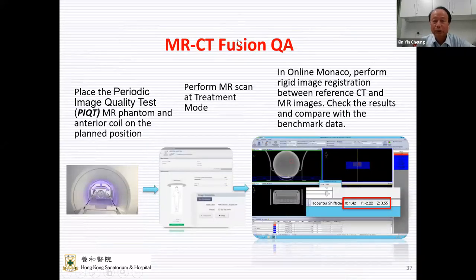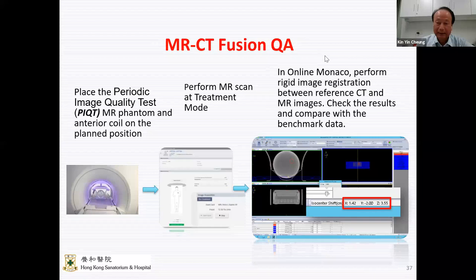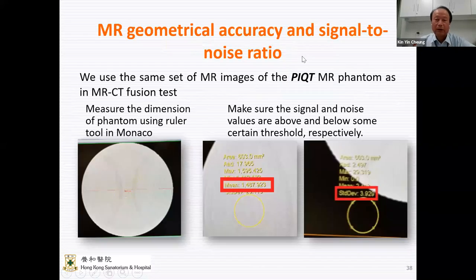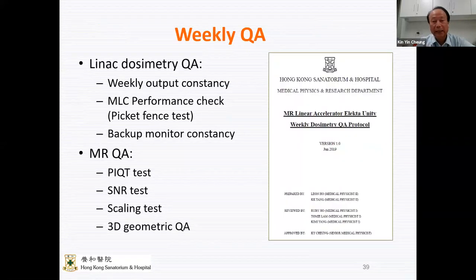And also we do MR and CT fusion, just to make sure that the adaptation planning is doable, that at least the MR is functioning and also the fusion software is functioning. And also we do a quality check on the MR image in terms of signal to noise and geometry. And then we go to the weekly QA.